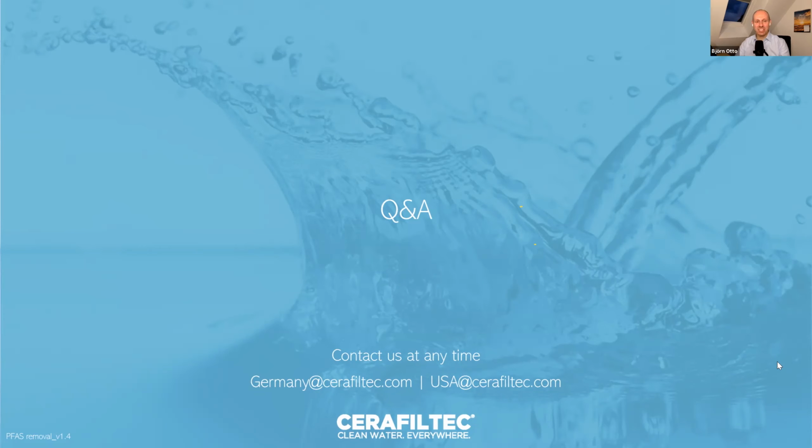All right. Sarah was asking, what is the maximum oil concentration? Boy, let's say this. If we get over 1,000 milligrams per liter, we would want to talk about whether it makes sense to have a skimmer upstream. So there's effectively really no limitation. It just is a question of what makes hydraulically economic sense. We do projects in several hundred milligrams per liter with free oil, so this is not a problem.